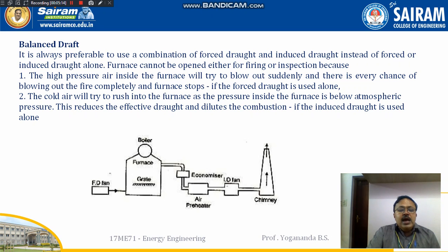On the other hand, the cold air will try to rush into the furnace as the pressure inside the furnace is below atmospheric pressure. This reduces the effective draft and dilutes the combustion process if you are using induced draft alone.